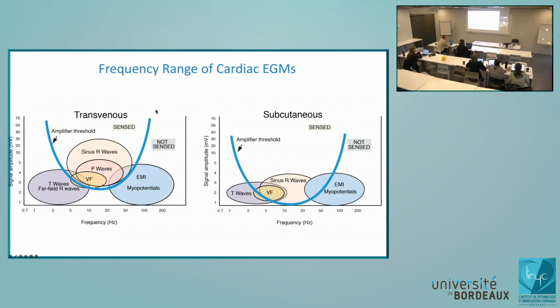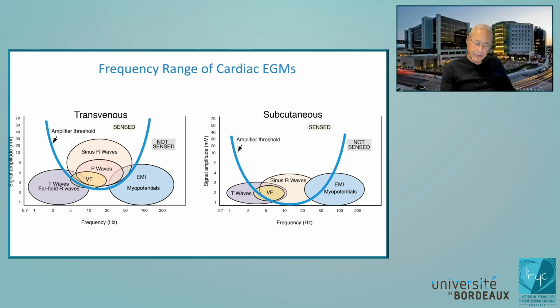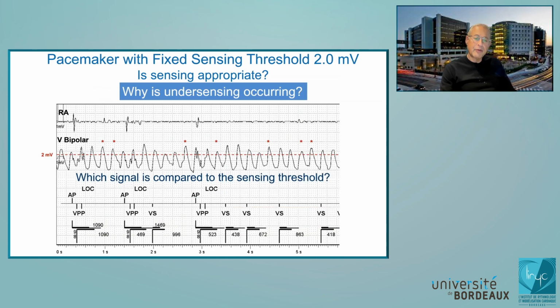Yes, please. I'm sorry to interrupt, but I have a question. The signal we can see on the controller, is it already filtered and amplified and modified, or is it the raw signal from the electrode? Yeah, so as I said a moment ago, it depends on the company you're looking at, and you should know which companies show you each. To be very specific, Medtronic shows you wideband unfiltered signals only. Boston and Biotronik show you only filtered signals. Abbott shows you both as options. The one they call V bipolar is unfiltered or wideband filtered. There's always a little bit of filtering, but yes. The one they call SenseAmp is narrowband filtered.